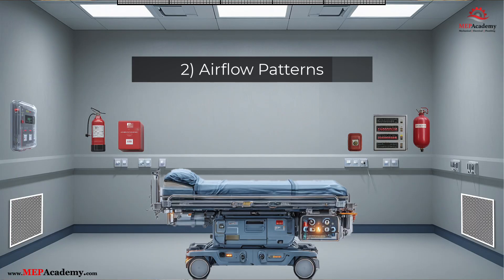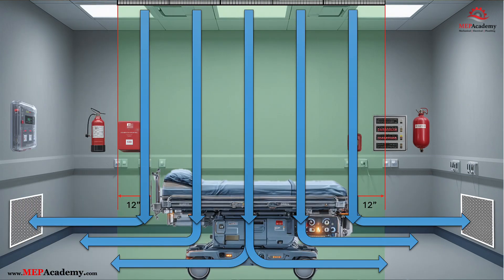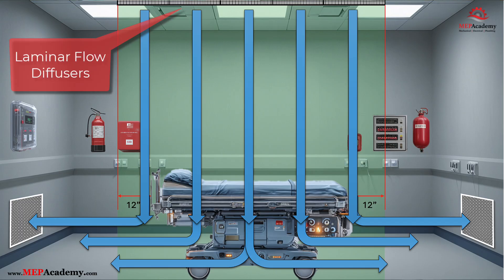Takeaway 2: Airflow patterns and HVAC layout protect the sterile field. The configuration and movement of air in an OR is not random — it's engineered to flush contaminants away from the patient and surgical team. Per ASHRAE 170-2021 and FGI guidelines, supply air must be delivered using a unidirectional laminar flow system located directly above the surgical table. Supply air enters the room through laminar unidirectional ceiling diffusers, located directly above the surgical table in the sterile zone, and is filtered through HEPA filters.